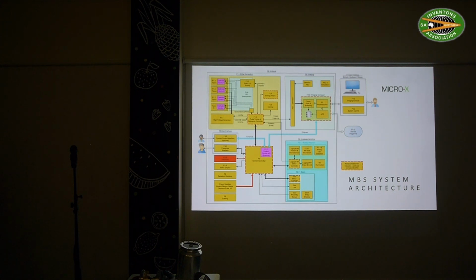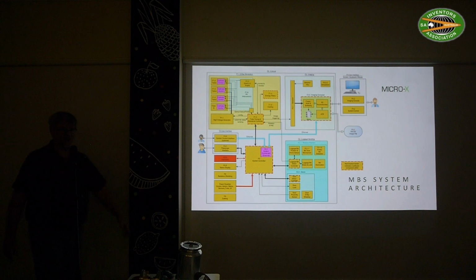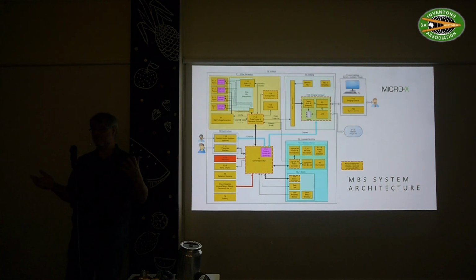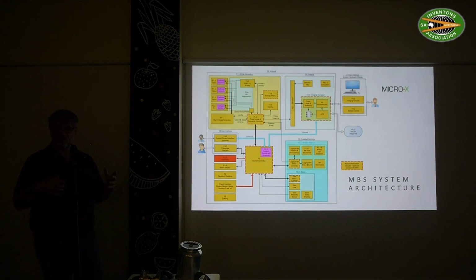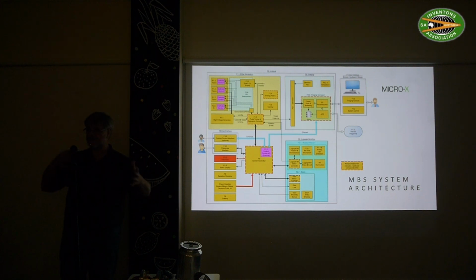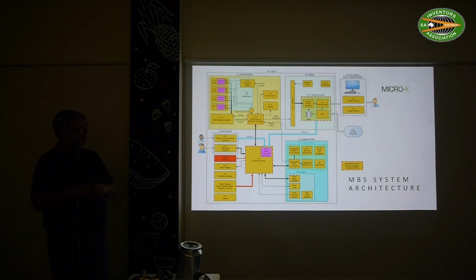But the next thing is that now we're talking about CT images. It means we take a lot of images, and the plan is we take 360 images when the bin spins around. We need to synchronize that in such a way that when the bin rotates, there's a signal coming from the bin that tells me exactly where I am every time, and then on the tube side it says, okay, when you hit position 375, I'm going to fire tube number 1.